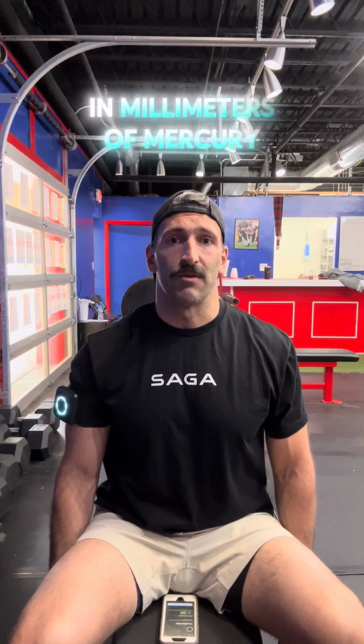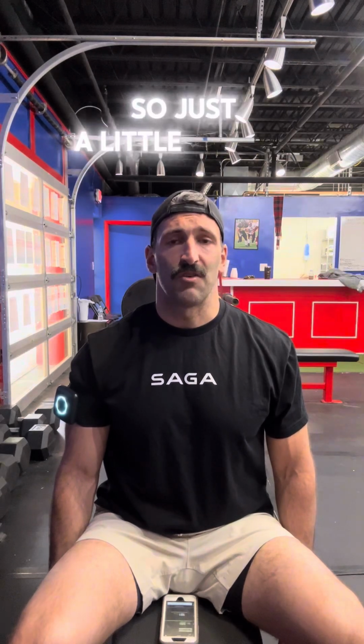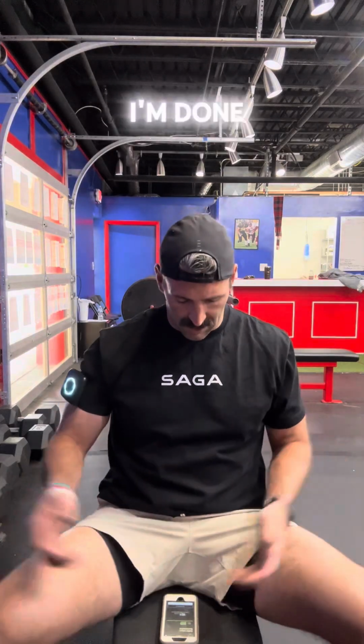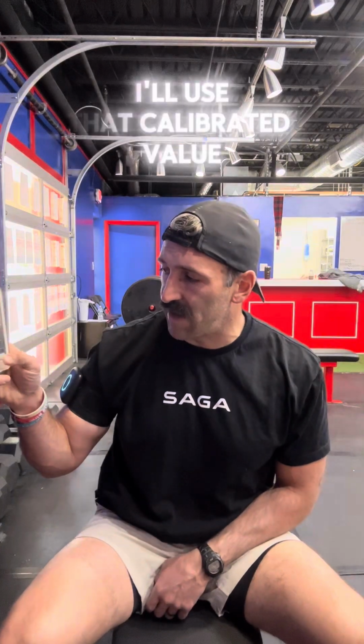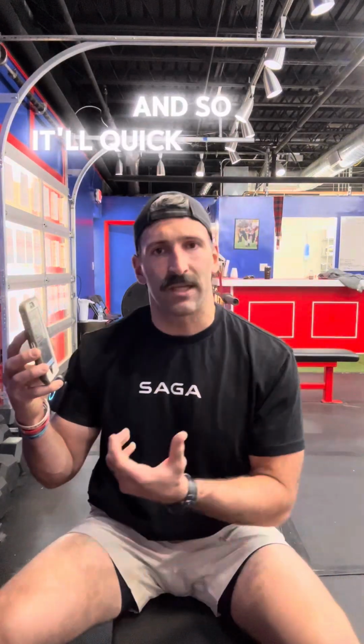Right, when that pulse is no longer picked up, that's what it marks as 100% limb occlusion pressure, and then it will provide that value. One of the most important things, and one of the reasons I love it, is it provides that value in millimeters of mercury. So just a little nuance. I'm done calibrating, right? There's my millimeters of mercury. Now I can recalibrate, or I can use that calibrated value. I'll use that calibrated value, and so it'll quick save that for me.